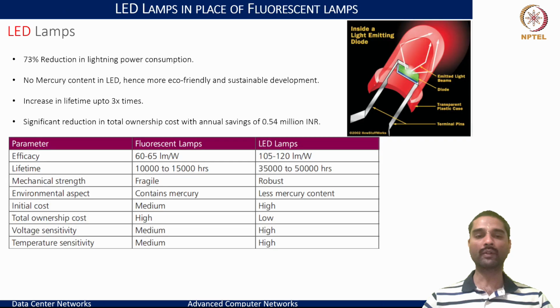Let's look at one of the prospects for lighting. This project from the DCiE tried to show that just replacing fluorescent lamps with LED lamps brings a lot of benefits, not just in power but also in overall capacity and cost planning, and in making development more sustainable and eco-friendly. Fluorescent lamps provide about 60 to 65 lumens per watt, while LED lamps provide 105 to 120, almost double the lumens per watt, and that's where the efficiency comes from.